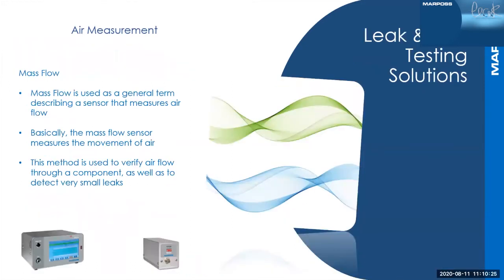Next, we start getting into air measurement with mass flow. Mass flow is a different technique from both pressure decay methods. It does not convert a pressure change to a flow reading. Instead, the mass flow sensor actually reads the flow across its element and provides a signal with the actual flow value. Mass flow can get a bit confusing when mentioned with leak test, meaning sometimes mass flow is used to verify a minimum or maximum amount of flow, and this is used to check for blockages or occlusions. Sometimes mass flow is used as a leak test similar to pressure decay leak tests.